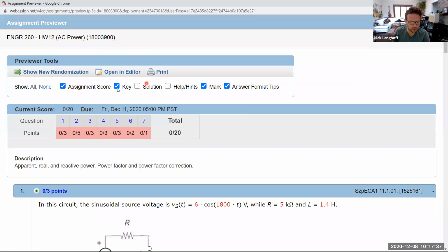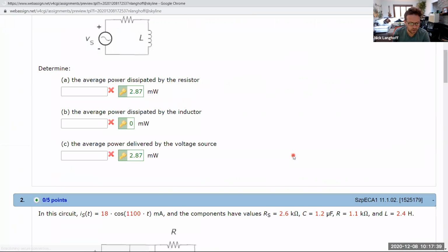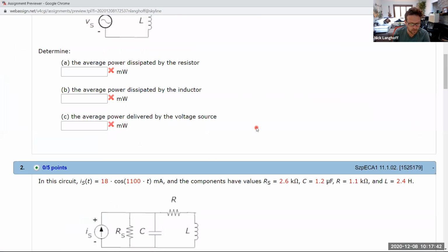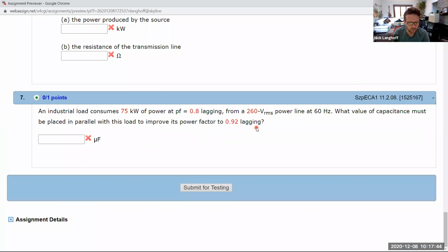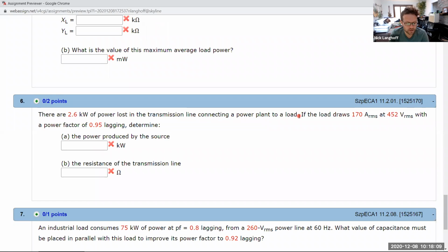If you're looking at the homework assignment, here's a similar problem: an industrial load consumes 75 kilowatts of real power at a 0.8 lagging power factor from a 260 volt RMS power line at 60 hertz. What value of capacitor do you want to put in parallel to improve its power factor to 0.92? That's really similar to the problem we just did.